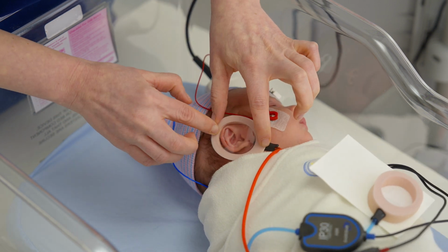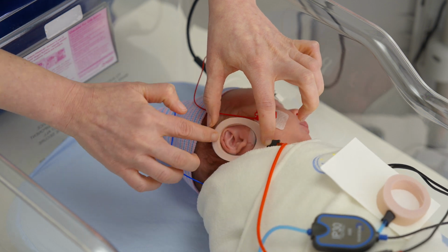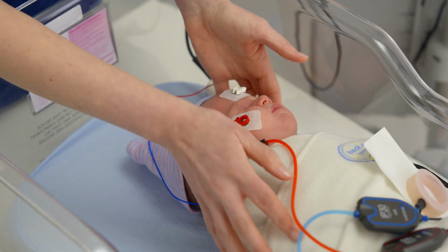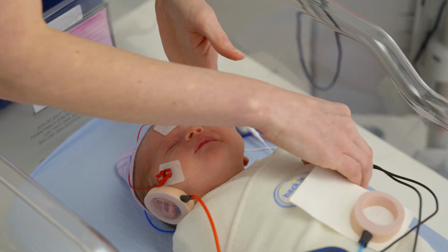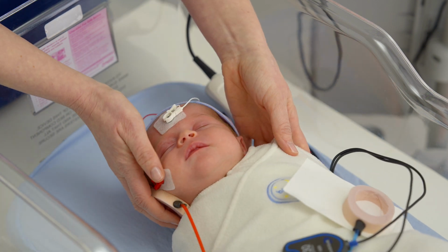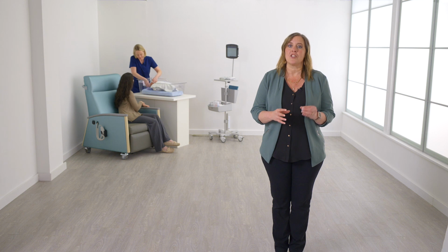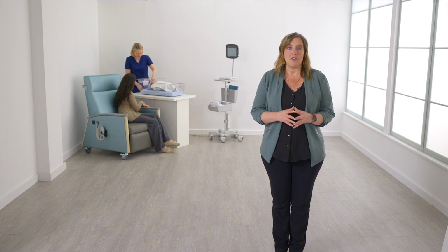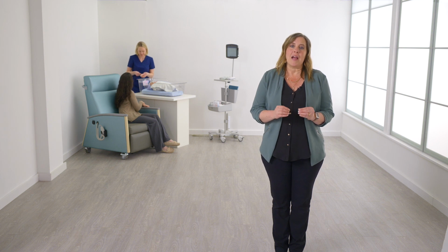If the ear cup is not sealed completely, or if the black adapter is partially blocked, the loudness of the clicking sound will be reduced and could cause a refer result. Repeat this process for the left ear by placing the ear cup attached to the blue tubing around the baby's left ear. If you are using insert phones with ear tips, inspect the baby's ear canal opening and select the appropriate sized ear tip. The red flanged ear tip fits most newborn ears.